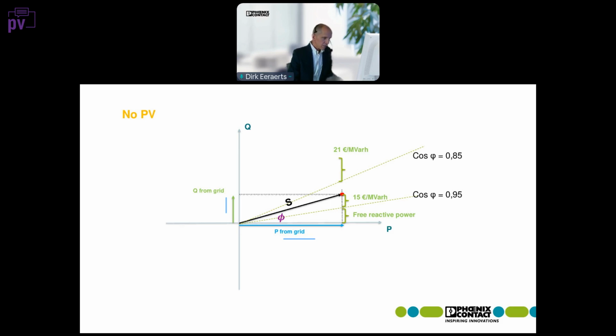And here are some numbers that are valid for Belgium. If your cosine phi or your power factor is above 0.95, you will get free reactive power. Between 85 and 95%, you have 15 euros as a fee per megavar hour. And if your cosine phi is below 0.85, so if it's really bad, then you will pay a higher fee.